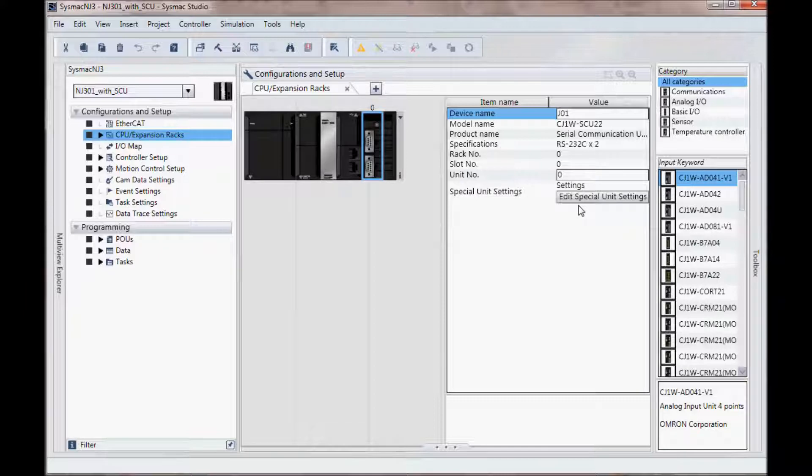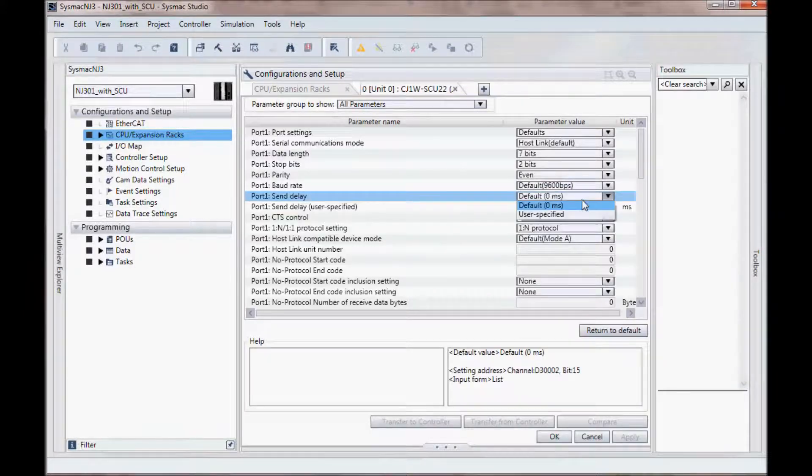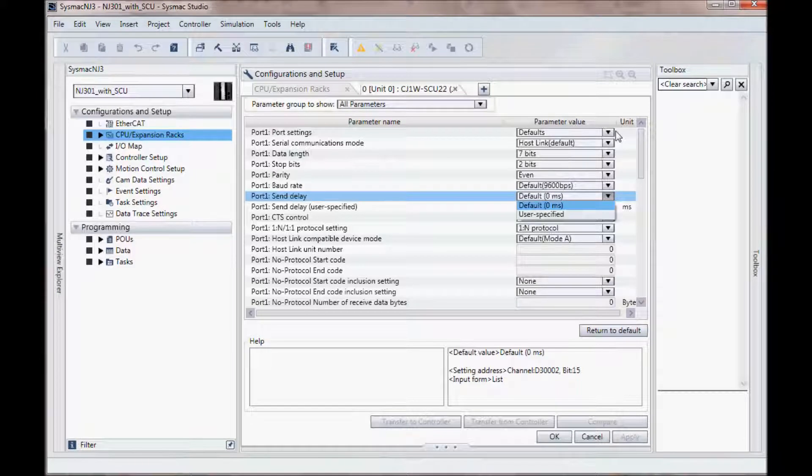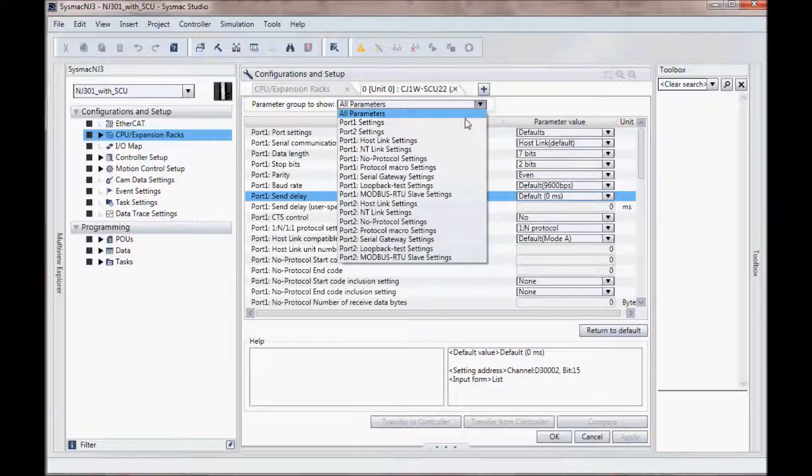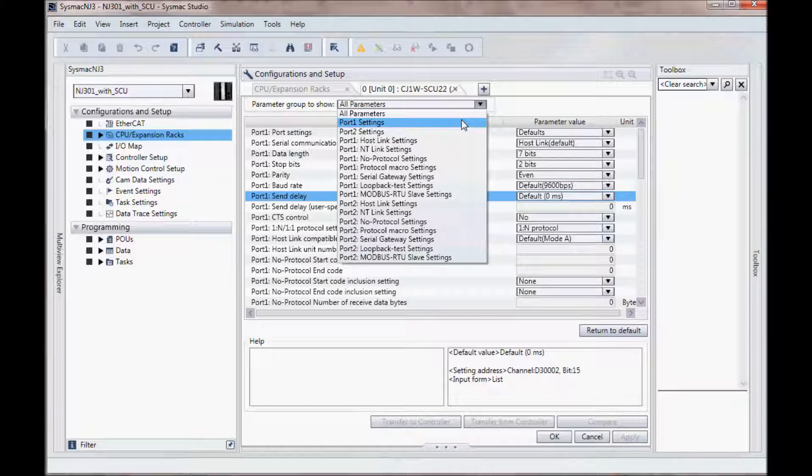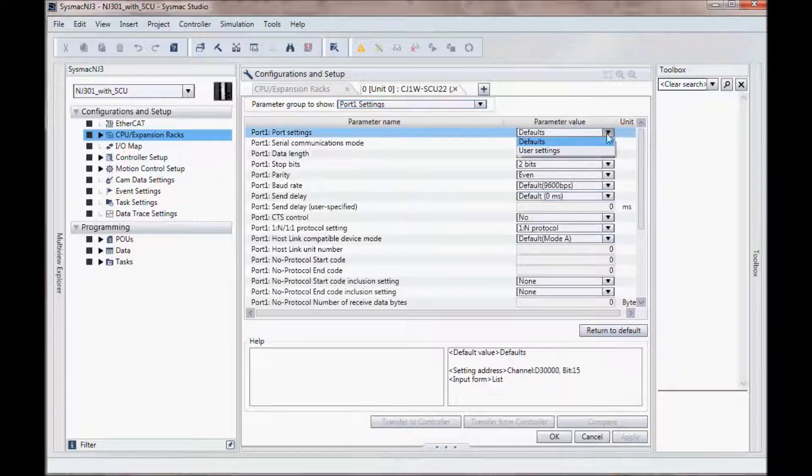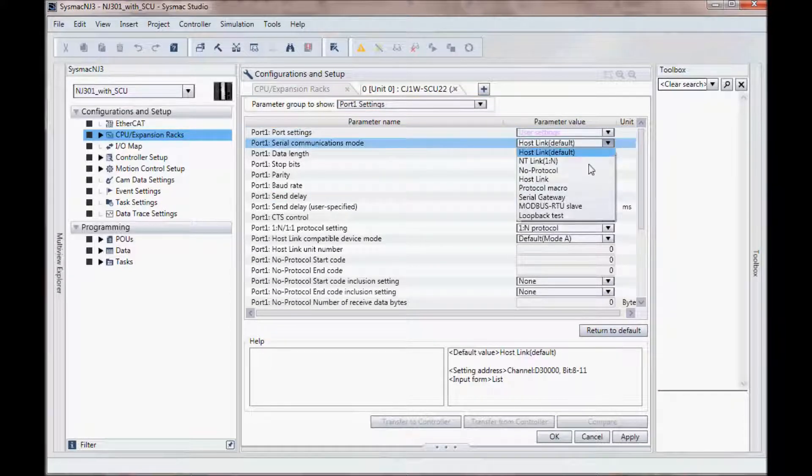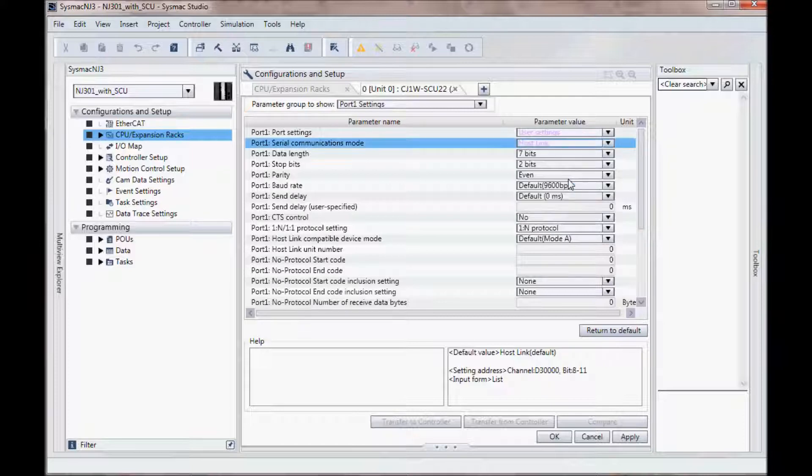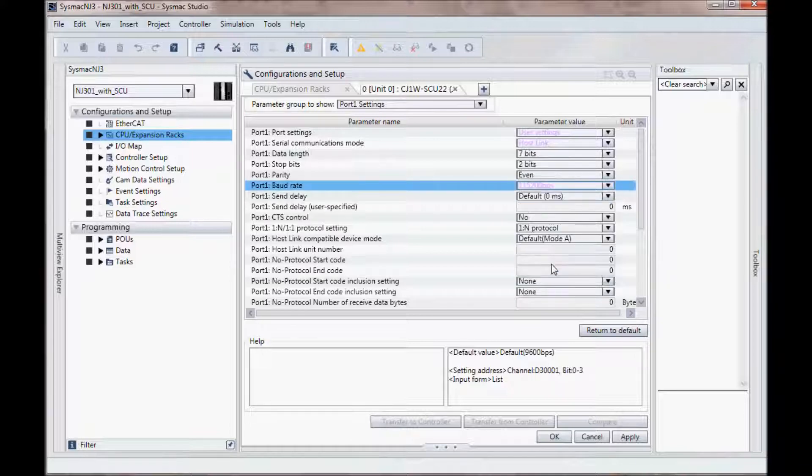I will double click on the edit special unit settings and I am going to look at port 1. There are two ports on this unit and I am going to select port 1 by going up here and selecting port 1 settings. I am going to use user settings and I will select host link and my baud rate I want to select 115k baud. I will now click OK.